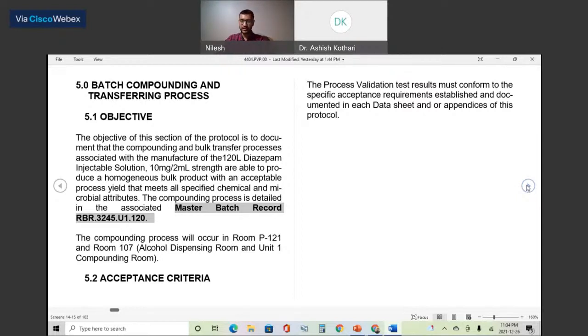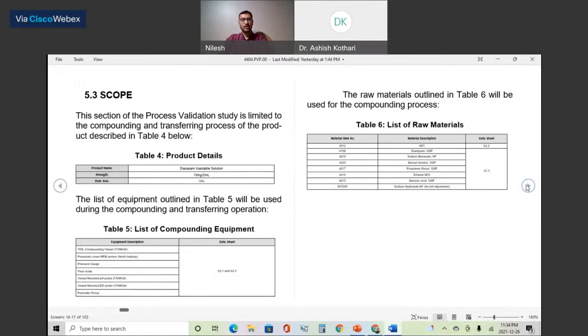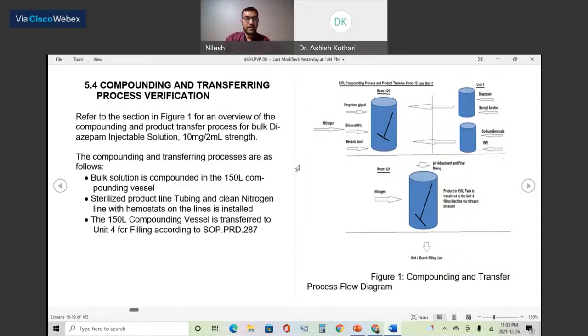They do the routine testing for the product which is already in the market, not at the stage of validation. So here you will again mention the equipment and product detail, particularly for the compounding or manufacturing portion. And you are seeing this data sheet; it will come later on, because I cannot explain it at this point without showing those data sheets. But for the compounding and transferring process verification, you have to prepare one flow chart.